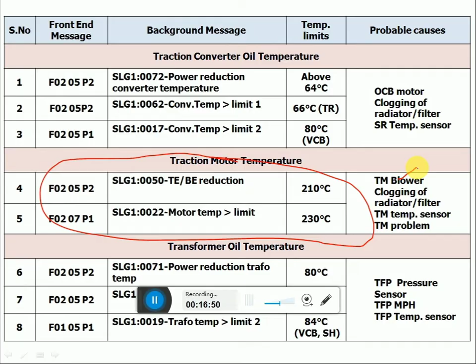You can see traction motor temperature too high. So we have to ensure TMB MCBs. TMB should be in working condition. The traction motor blower should be in working condition, and their MCB should be in good condition. If any tripping, we can reset. Different messages when traction converter oil temperature too high: we have to ensure working of OCB and traction converter pump and TFP pumps. Traction motor temperature too high means we have to ensure working of the TMB blower.